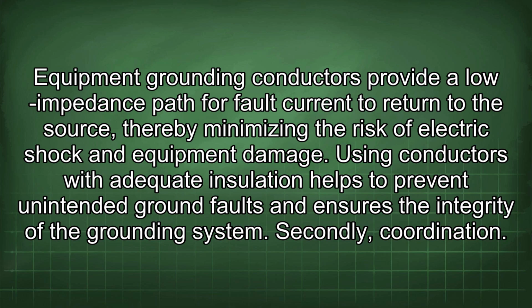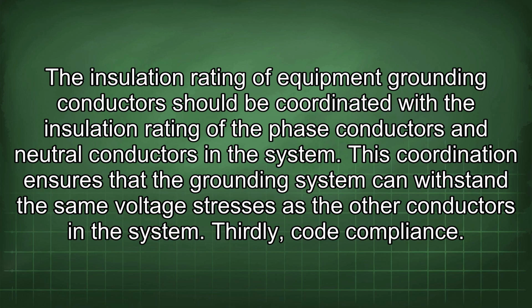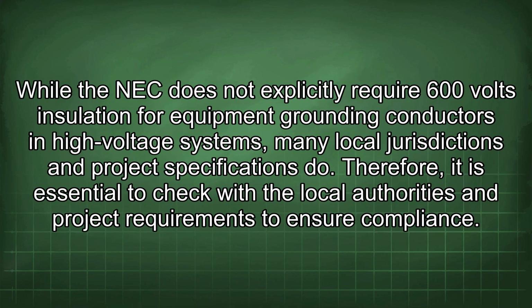Secondly, coordination. The insulation rating of equipment grounding conductors should be coordinated with the insulation rating of the phase conductors and neutral conductors in the system. This coordination ensures that the grounding system can withstand the same voltage stresses as the other conductors in the system. Thirdly, code compliance. While the NEC does not explicitly require 600 volts insulation for equipment grounding conductors in high voltage systems, many local jurisdictions and project specifications do. Therefore, it is essential to check with the local authorities and project requirements to ensure compliance.